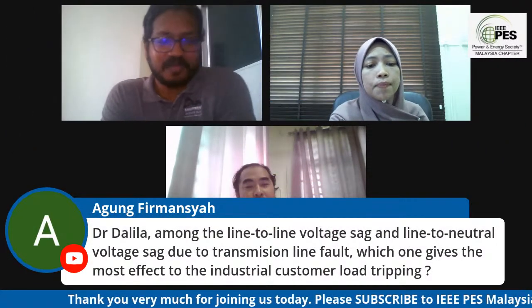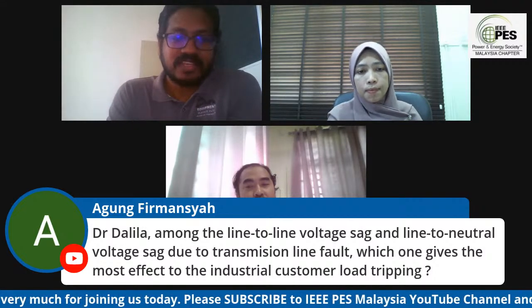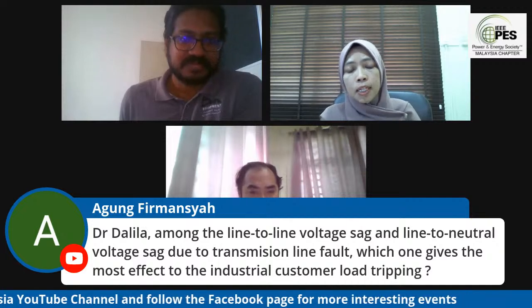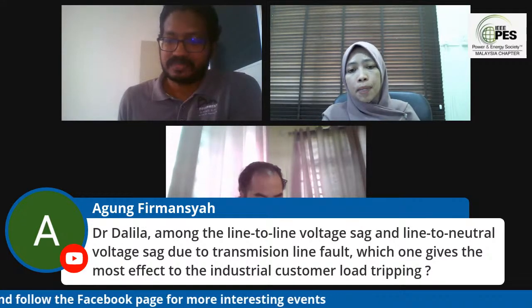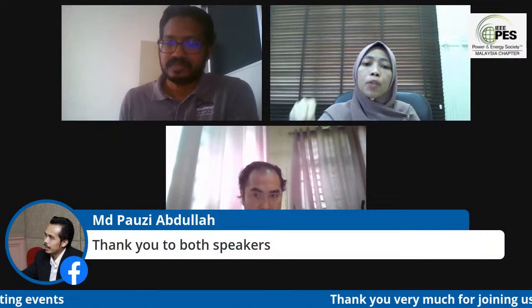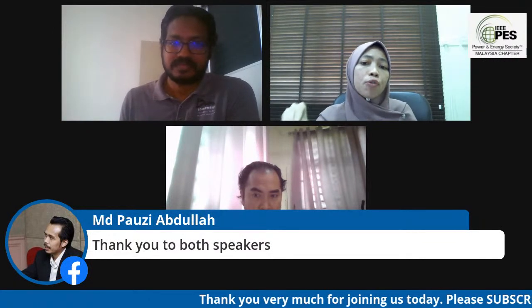Dr. Dalila, this question is from Che Agong. Between line-to-line voltage sag and line-to-neutral voltage sag due to a transmission line fault, which one gives the most effect to industrial customer load tripping? Okay, it depends. When considering the type of fault, the impact on industrial equipment depends on that industry's immunity level. If all the devices and equipment follow the standard, they may not be impacted by the event.